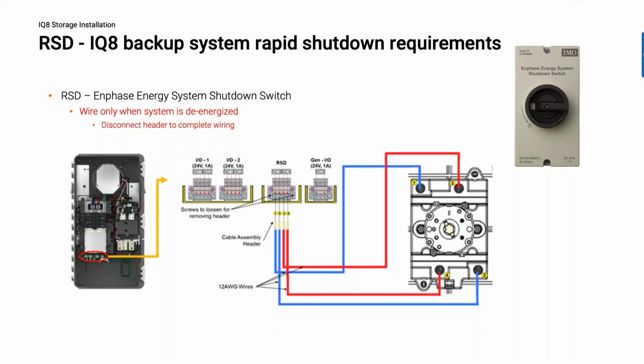Now, when you wire this, you should never wire this when the system is live. If you have rewired a customer's home and the system is up and running, installers sometimes are hesitant to have to shut down the customer's home again. And so you try to wire this switch in to get it working, and you do it when the system is live and energized. And that is absolutely something you should never do, because what happens is if you wire this live and you touch a ground line inadvertently, I mean, you can be really careful about this, but there have been so many instances of a short happening, and what'll happen is it'll damage a component within the system controller.